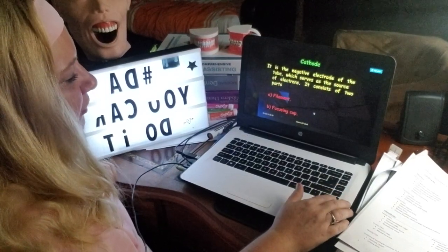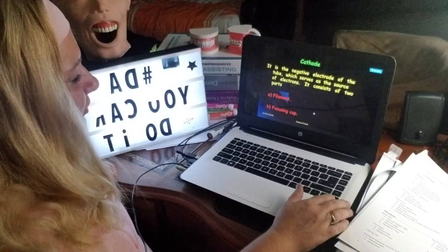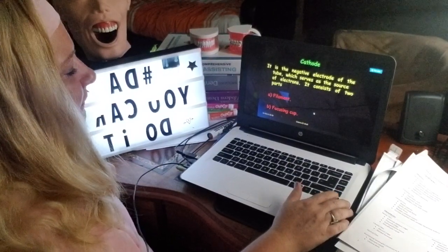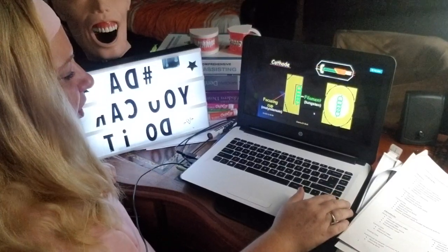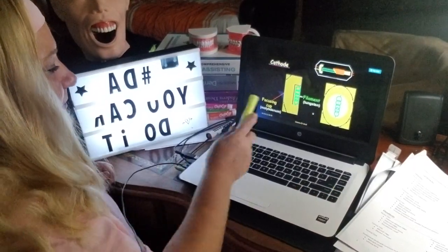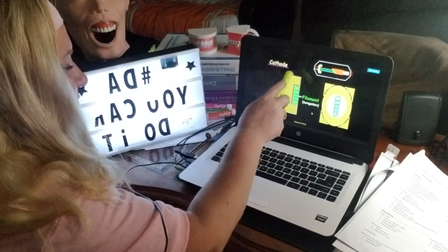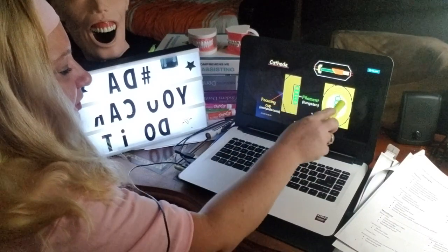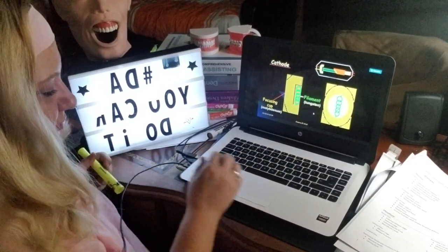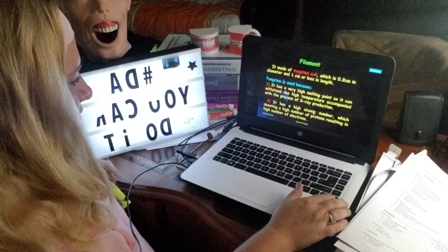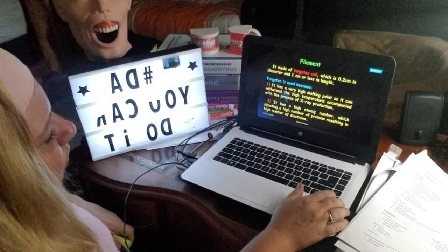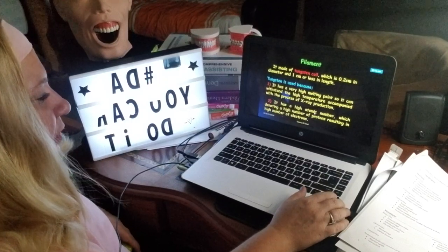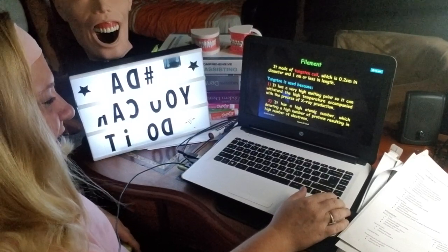The cathode is the negative electrode of the tube, which serves as the source of electrons. It consists of two parts, the filament and the focusing cup. The focusing cup is right here, and then the filament is this. The filament is made of a tungsten coil, which is 0.2 centimeters in diameter and 1 centimeter or less in length.